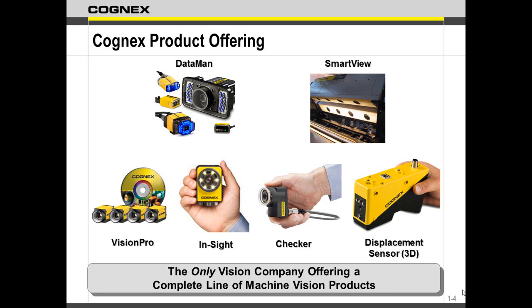We have Checker. Checker is kind of a smart sensor. Presence, absence, is something there, is something not there. It can also do some limited measurements, but once again, the measurements are always relative. They can't tell you that's 22 millimeters, but what they can tell you is if it's within the level that you stated. Now, if you change your focusing or where your camera's placed, then all bets are off with that one.